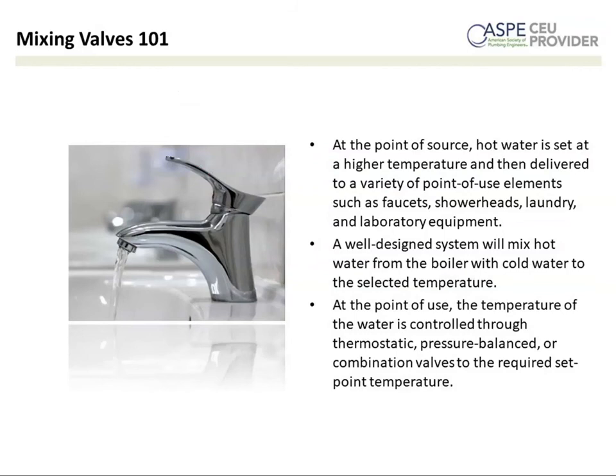So at the point of source, hot water is set at a higher temperature and delivered to various point of use faucets, shower heads. We've already talked about that. A well-designed system will mix hot from the boiler or the hot water heater and cold water, and it's very similar operation at the point of use. The temperature of the water is controlled through actually 3 different types of valves, depending on the application. If you're at a shower or a combination tub shower, it could be thermostatic, it could be pressure balancing, or it could be a combination valve.